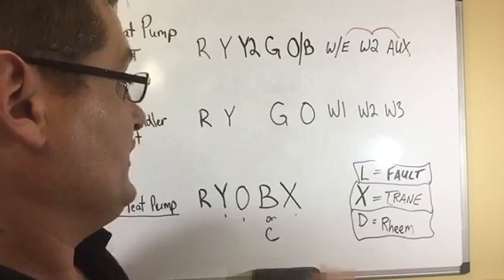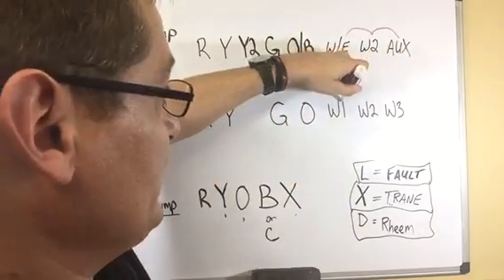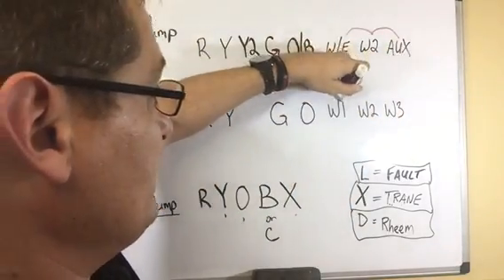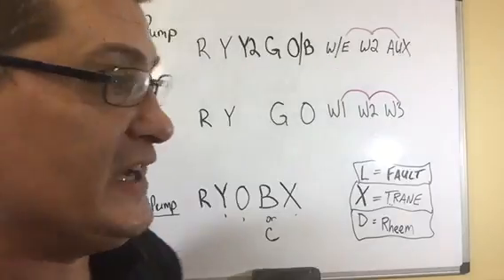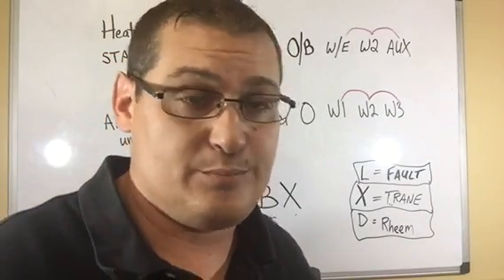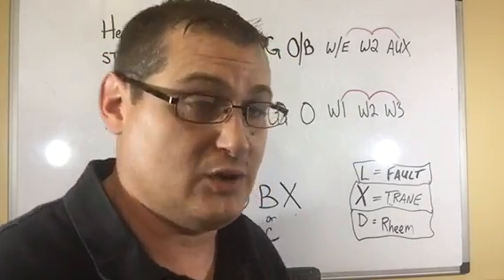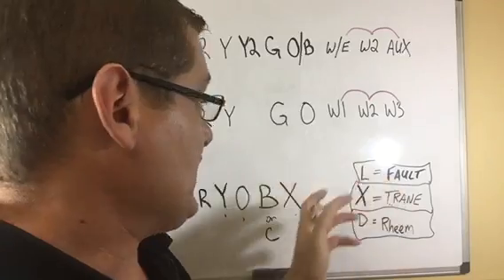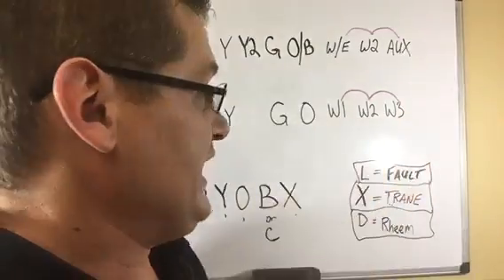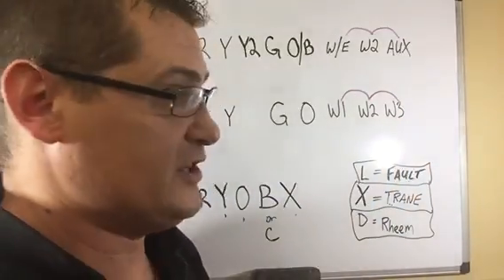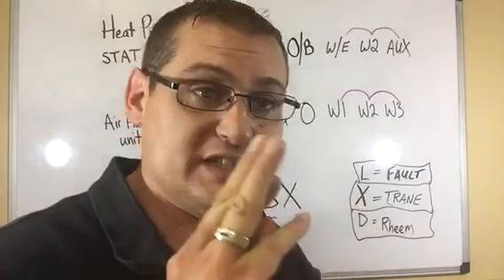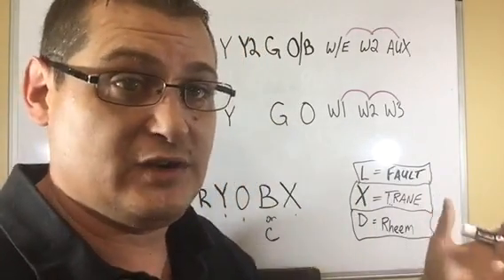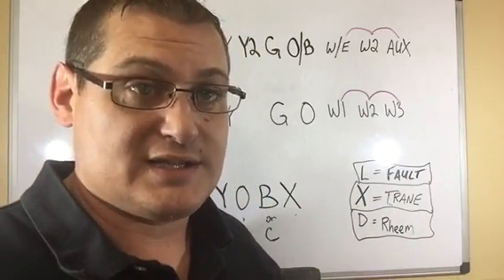At the thermostat or the air handler, if we've got W1, W2, W3, those are all just to power the strip heat. In certain Rheem units, this is what they actually had: W1, W2, W3. We just tied them all together with a wire nut and then hooked our white wire, because it's W from the stat, we would hook those up together.